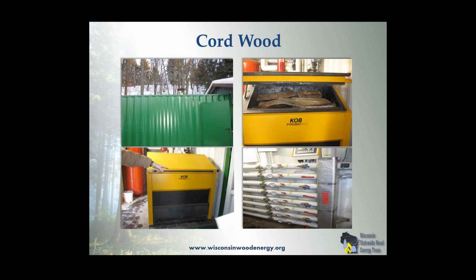Again, there's lots of appliances out there. There's a plug and play where you can just drop off. You see that green container or green storage container. Inside of that is a thermal storage unit, all the pumps and controls, and this KOB boiler, wood boiler. It's about a 500,000 BTU an hour system. You can see on the right they have distribution. In this case, where this is assembled, I think that's distribution to 3 facilities, supply and return, and there's an option for a 4th facility set up there.